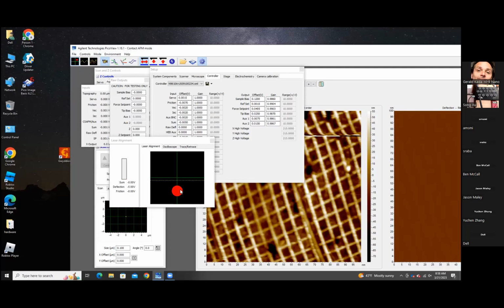When you go to STM, Song, can you set your sample bias to -1 real quick? Set sample bias to -1. There, now you're aligned to your yellow line. So it's actually at -1 volt. It's a reminder. When you're doing contact mode, you want to make sure that you are at least below -1 on your deflection in contact. That's what the yellow line's there for. It's to remind you that you need to be on or below that line for your contact mode to work properly. Correct. Okay, thank you.